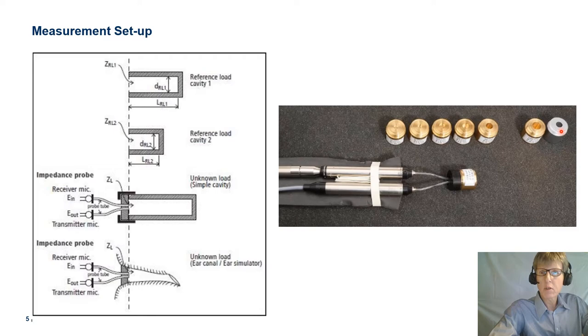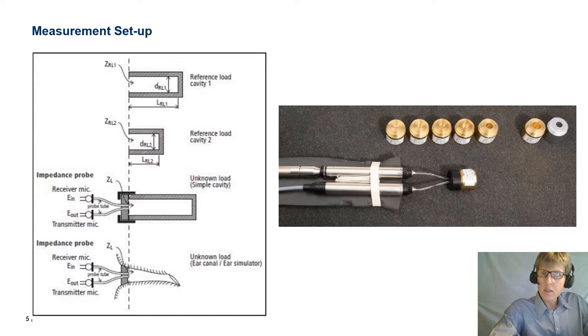The limitations associated with the two-load method are that it starts to break up when the frequency approaches the first anti-resonance, which typically happens around 5 to 6 kHz in a typical human ear canal, and that it tends to generate a non-physical negative resistance. So improvements were required before we could use the method for measurements on humans.